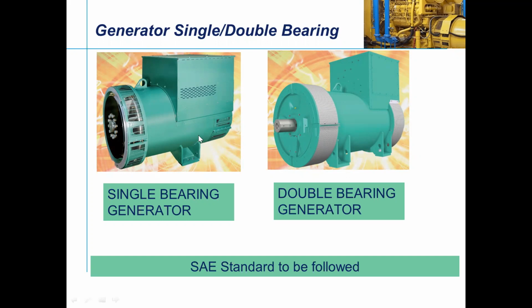Presently, all engine manufacturers you can name, from Caterpillar or Cummins engines to Mahindra or Ashok Leyland, go with these SAE standards, wherein the coupling mating point is well matched. The marriage happens in a better way. Coming to the turbine segment, of course, with a steam turbine or hydel or marine application or shaft generators, the double bearing is preferred for the torsional value and torque sharing. So this is what I am talking about. You can see that the alternator is coupled to the engine prime mover, and you can see the rotation of the prime mover and the alternator.